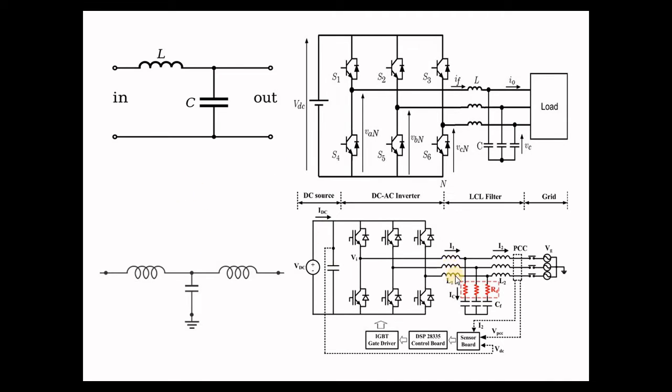Sometimes we can connect an LC filter to the grid also, but mostly we follow this, because if it is grid connected and I connect an LC filter, then there is no grid side L here. The capacitor will work as a load on the grid, because the grid is directly connected to the shunt capacitor. So the capacitor will act as a pure capacitive load on the grid.